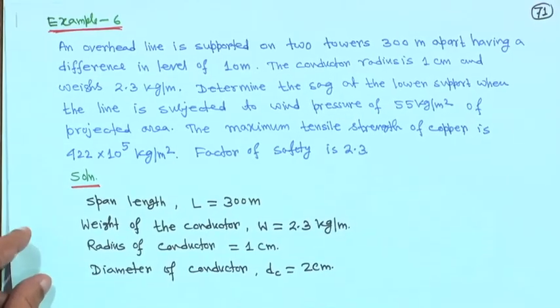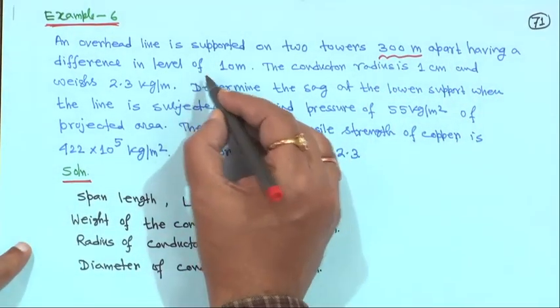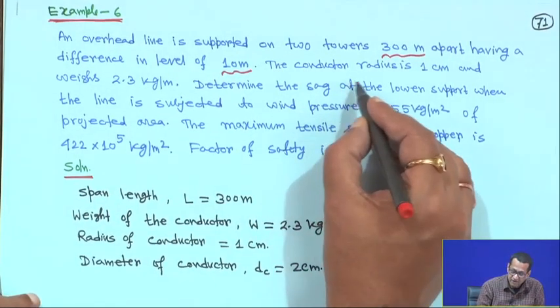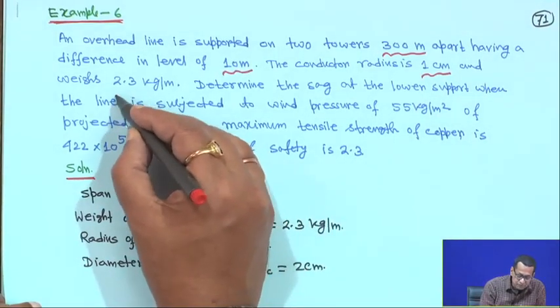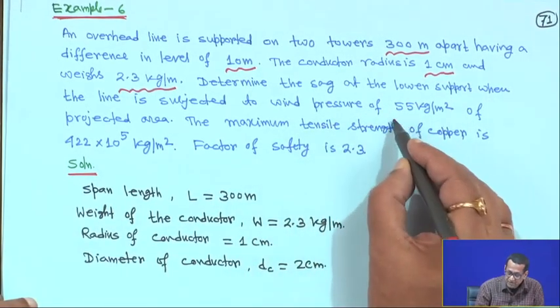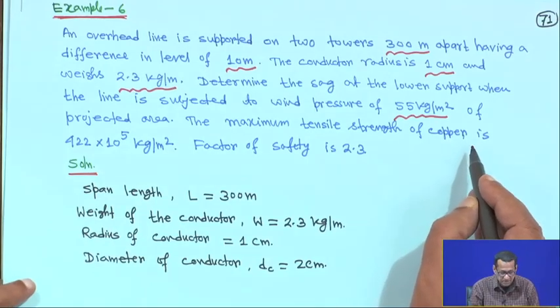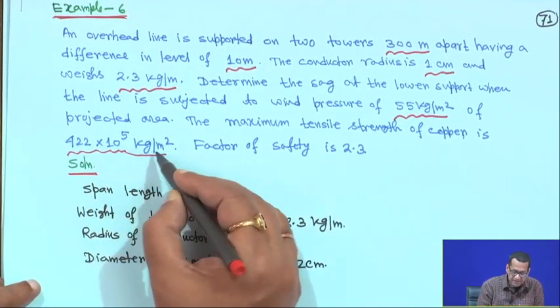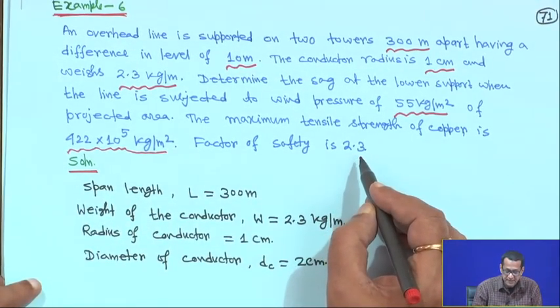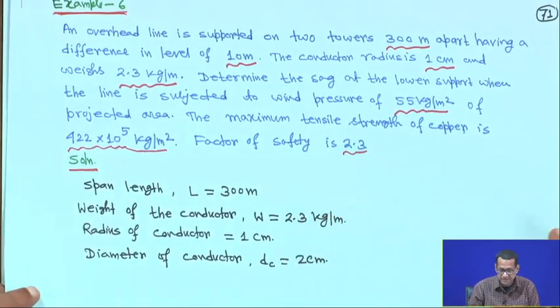Next we take example 6. An overhead line is supported on 2 towers 300 meter apart, having a difference in level of 10 meter, so they are not at the same level. The conductor radius is 1 centimeter and weight is 2.3 kg per meter. Determine the sag at the lower support when the line is subject to wind pressure of 55 kg per meter square of the projected area. The maximum tensile strength of copper is 422 into 10 to the power 5 kg per meter square and factor of safety is 2.3.